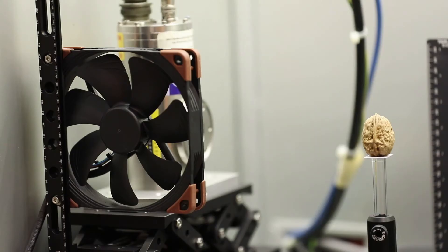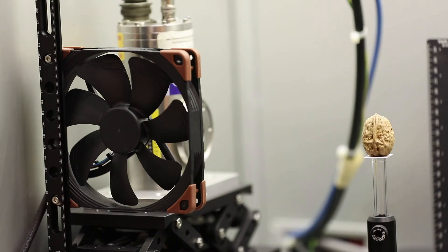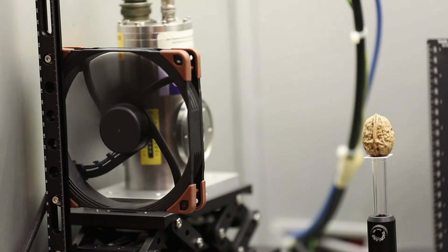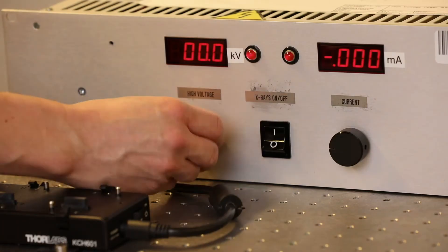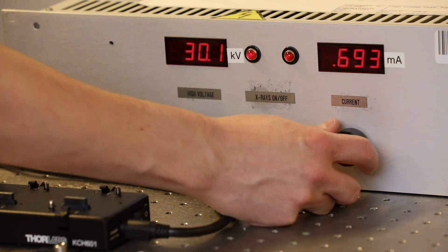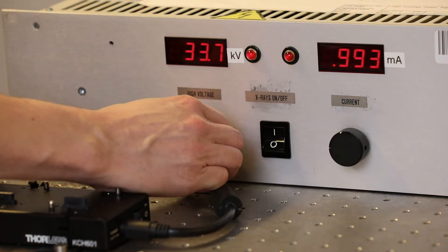However, less than 1% of the kinetic energy of the electrons is converted into x-rays and the rest goes into heating the anode. That's why it's very important to ensure adequate cooling of the x-ray tube so that it doesn't overheat. The x-ray source in this scanner can be used with acceleration voltages ranging from 0 to 50 kV.